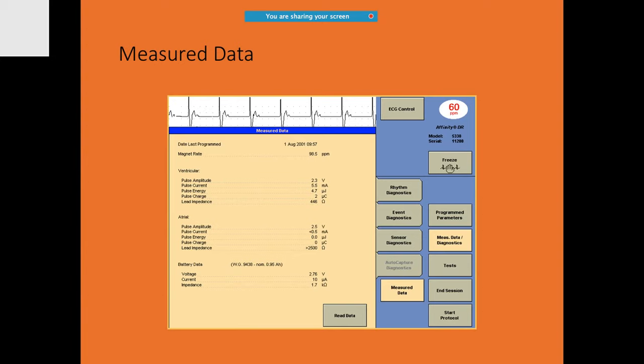For example, the various parameters you measure include: pulse amplitude, pulse current, pulse energy, pulse charge, and lead impedance. This applies not only for the atrial but also for the ventricular leads. And on the basis of that you will be able to see the battery data in terms of voltage, current, and impedance.